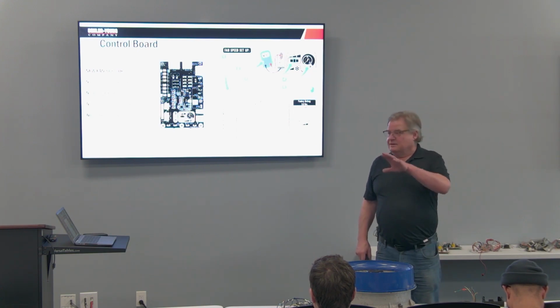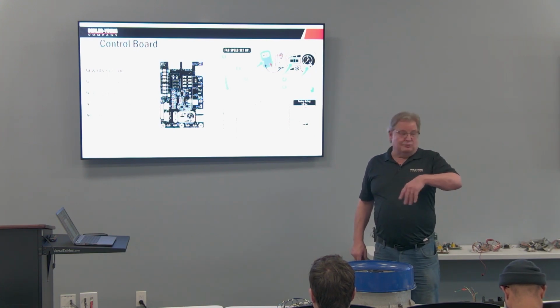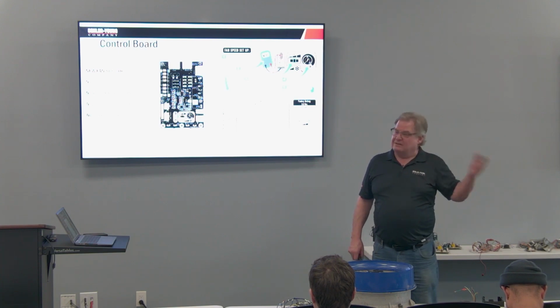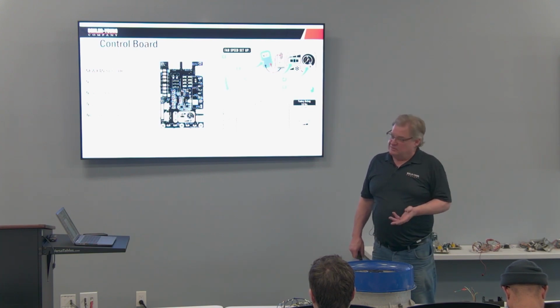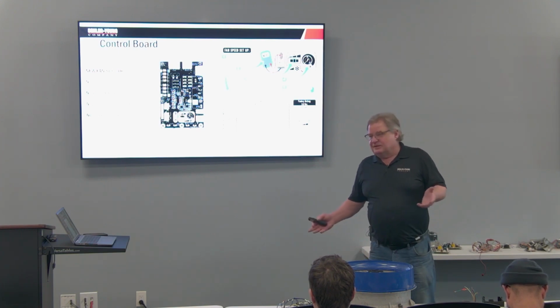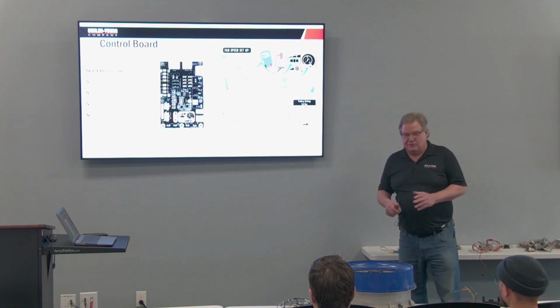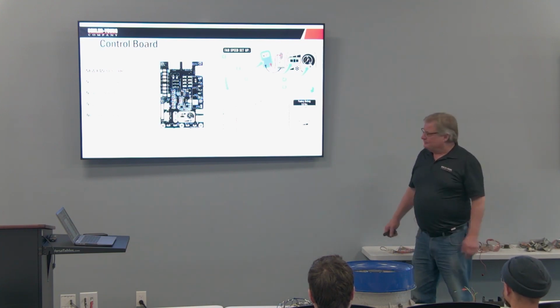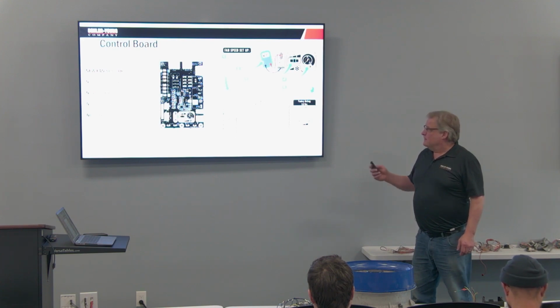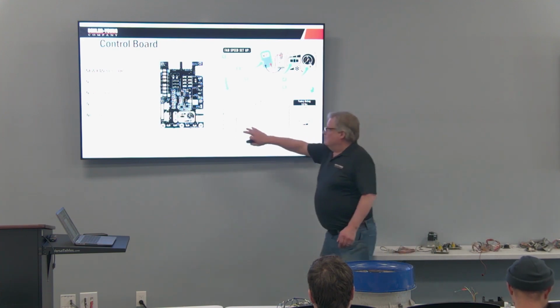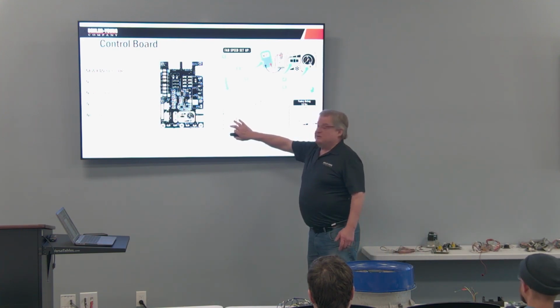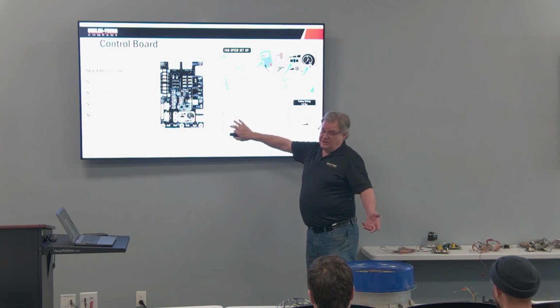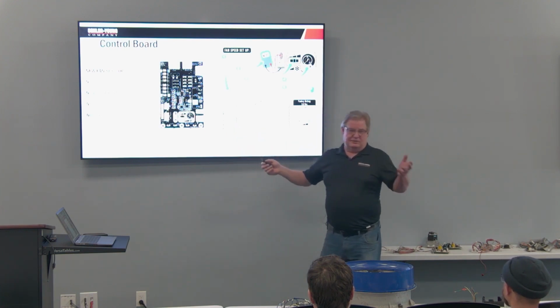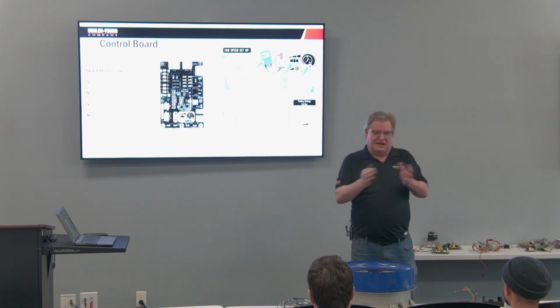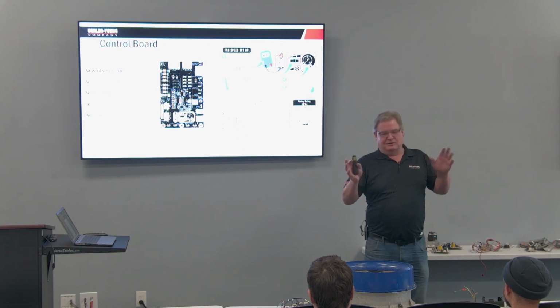So now, if you're just an installer and you don't care about your service guy coming back 3 times over the next 2 years trying to figure out why the blower motor keeps quitting, then this doesn't apply to you. But hopefully you're a little bit more concerned than that. So, 2,000 CFM. Everybody know how we figured that out? And if you're not sure what tonnage the unit is, it's always one number less than what it says on the tag. I don't quite know how that worked out.